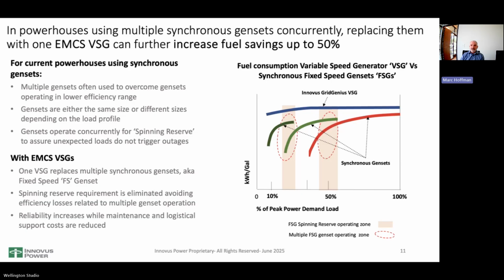So utilities or operators of powerhouses have to figure out how to deal with that. If you size the genset for peak load, which may be 700 kilowatts in wintertime, you might run chronically below minimums in summertime—and you can't do that and have those gensets be reliable.